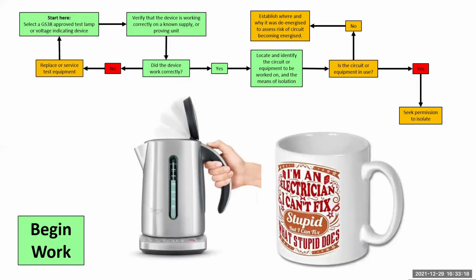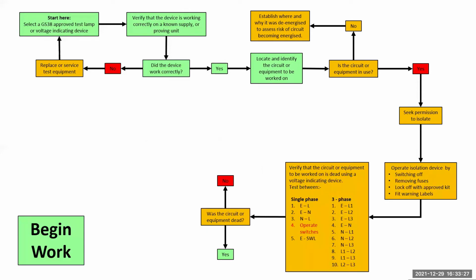Another little tip that I suggest is to offer to get the apprentice to stick the kettle on. And that way, when the tea is ready, everyone comes to a natural stop and you can switch the power off without argument. Once we have permission, we can operate the isolation device and fit our locks and warning labels so that we can safely test. Once the lock and toggle are on, give it a firm tug and wiggle to ensure that no one is able to interfere with your control.